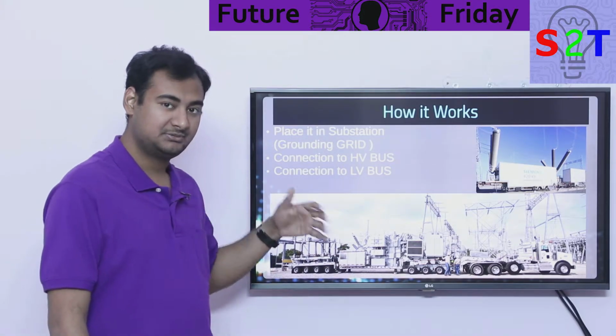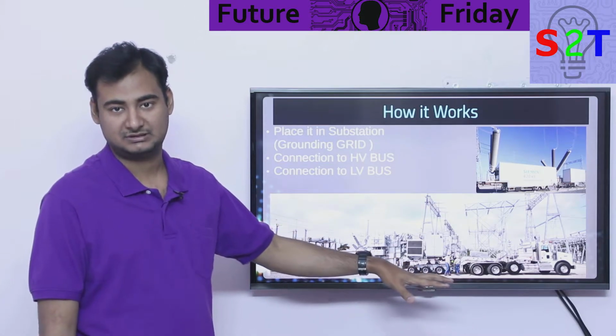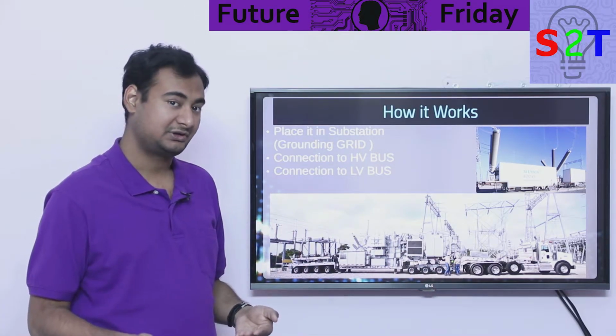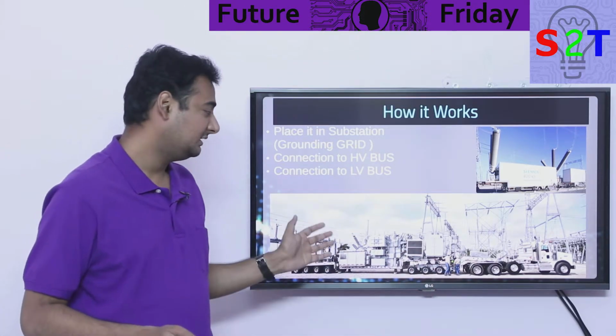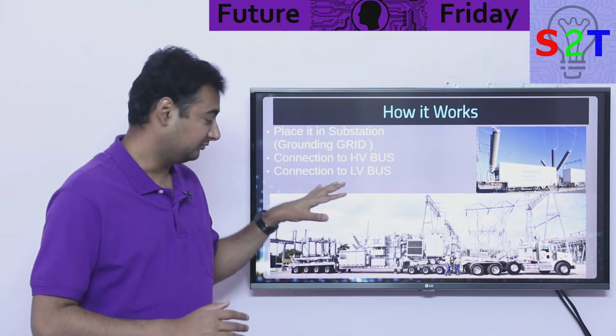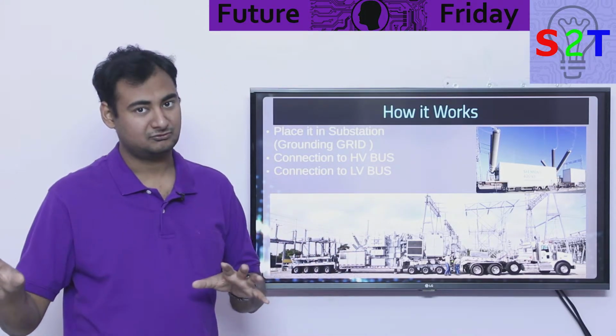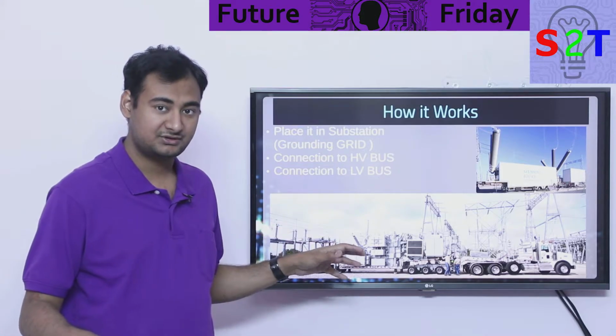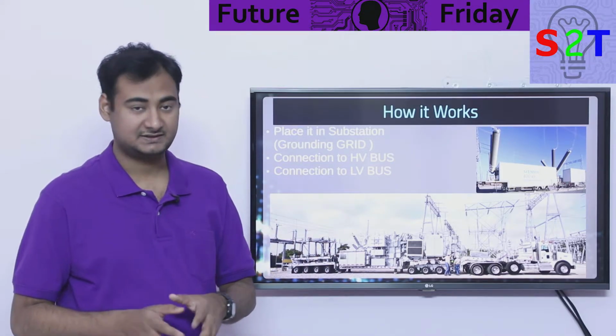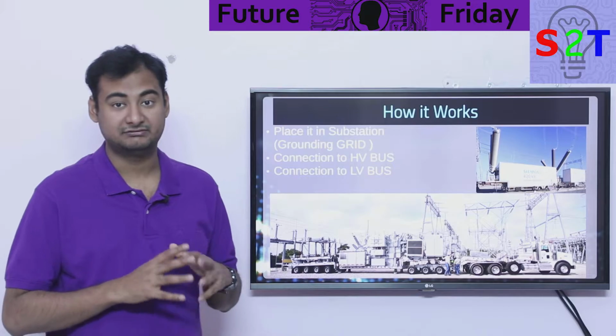Then you're gonna call these people up. It's like, okay, bring me a substation, of course with the appropriate rating. The rating must match, and then you're gonna connect it. During that time it's carrying the load, your perfect transformer is working, your mobile transformer is working, and the damaged transformer can be replaced. These puppies are designed to work for a very long time.